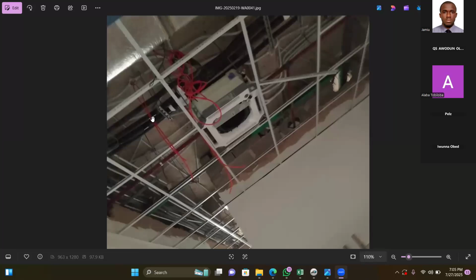Now, you can see this black stuff is where our refrigerant pipe is coming from. Like I said earlier, sometimes you might have 2 refrigerant pipes, sometimes 3. We have the liquid, we have the gas, and we have the aux. When you have 2 refrigerant pipes, you have the liquid and the gas. But when it is 3, the third one is the hot suction. Are we getting my explanation? Yes, sir. Now, this is our ceiling cassette, and all these black aspects are the refrigerant pipe linking from one ceiling cassette to another ceiling cassette or concealed unit.